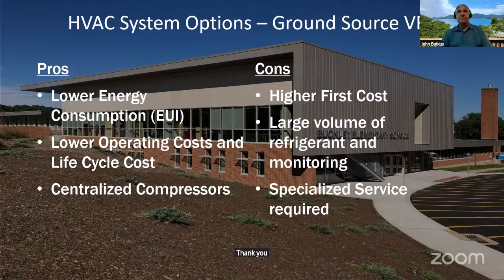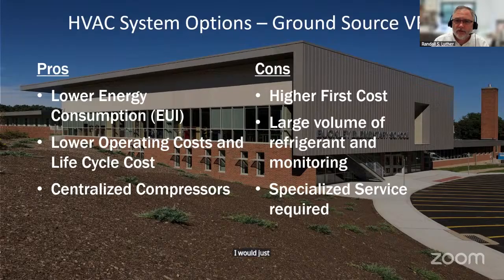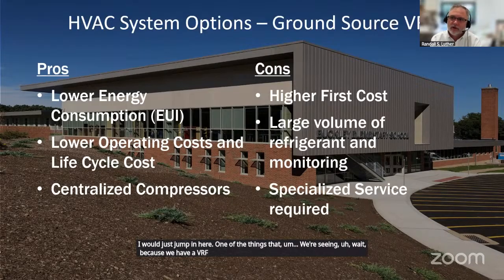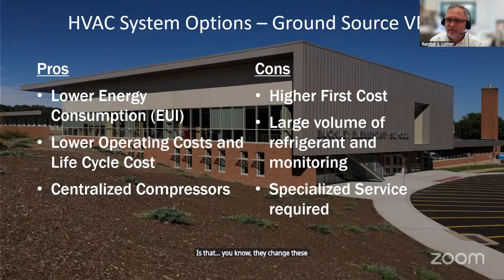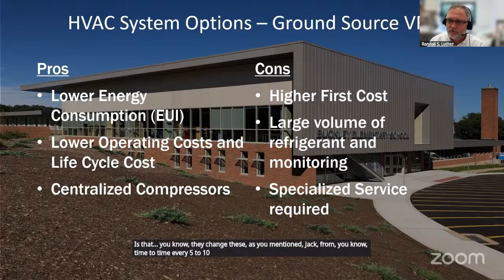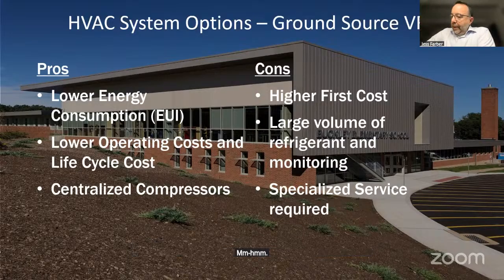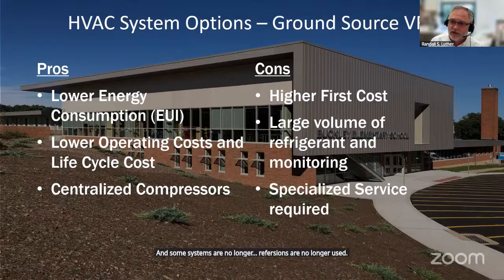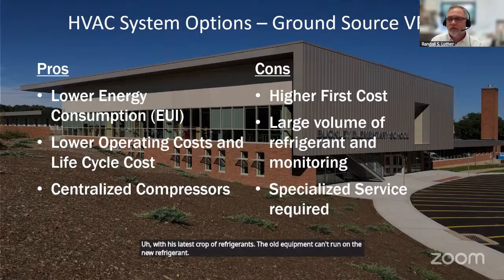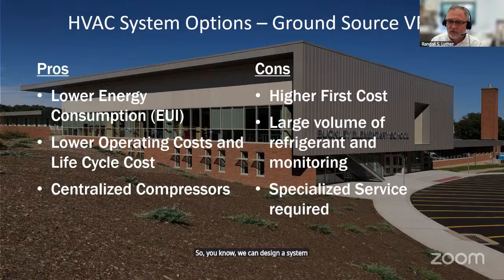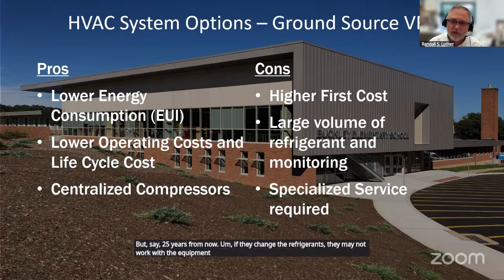One of the things we're seeing, because we have a VRF project right now under construction, is that they change these refrigerants from time to time. Every 5 to 10 years new regulations come out, and some refrigerants are no longer used. With this latest crop of refrigerants, the old equipment can't run on the new refrigerant. So we can design a system that works with refrigerants today, but say 25 years from now, if they change the refrigerants, they may not work with the equipment you still have in your building.